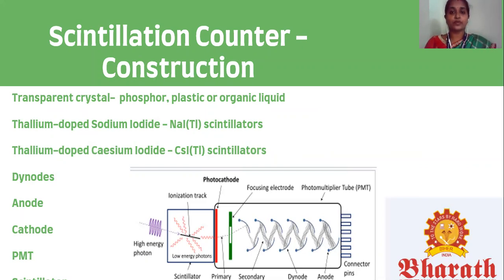The basic principle of operation involves the radiation reacting with a scintillator, which produces a series of flashes of varying intensity. The intensity of the flashes is proportional to the energy of the radiation. This feature is very important, and these counters are suited to measure the energy of gamma radiation, gamma spectroscopy, and therefore can be used to identify gamma emitting isotopes.